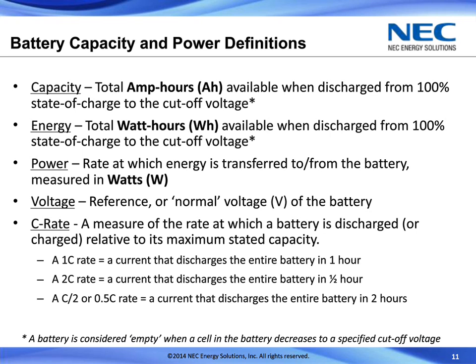And then a concept to understand is called C rate, which is a measure of the rate at which a battery is discharged or charged relative to its maximum stated capacity. And this is a way for us to use the language of what the battery is capable of, independent of the size of that battery. A 1C rate means a current that discharges the entire battery in 1 hour. So it's a combination of the rate and the time. A 2C rate would be a current that discharges the battery in half an hour. And a C over 2, or 0.5C rate, is a current that discharges the entire battery in 2 hours. So a C over 2 would be a 2-hour duration. A 1C rate would be a 1-hour duration. And a 2C rate would be a half-hour duration, and so forth.